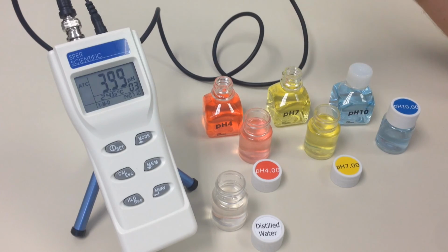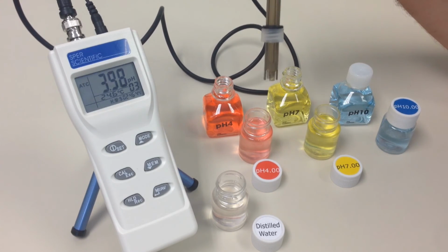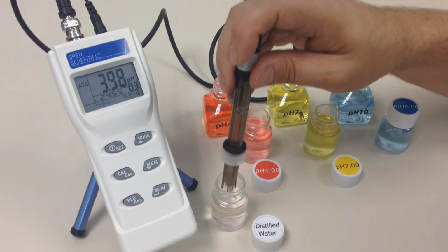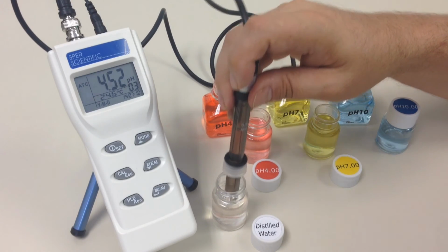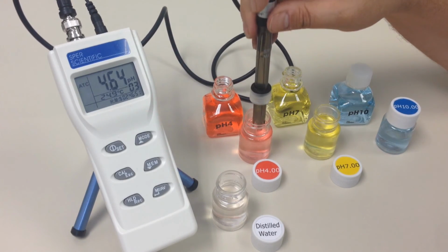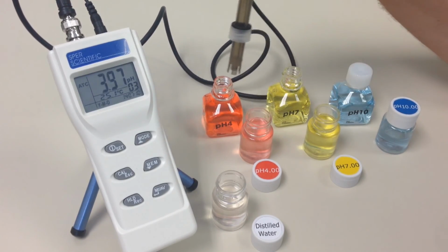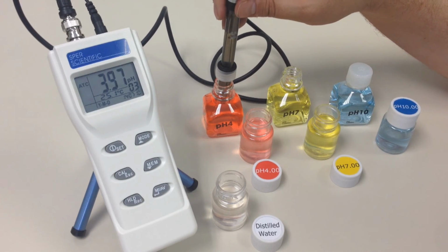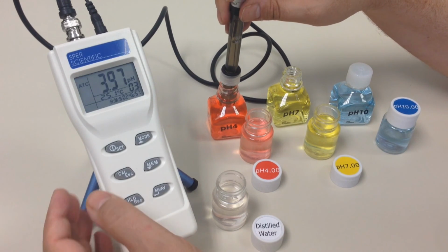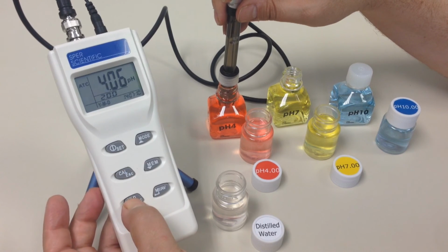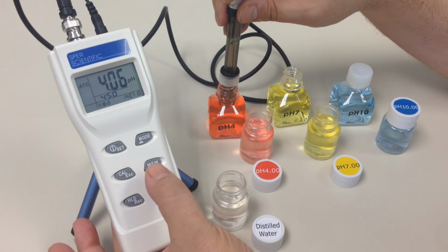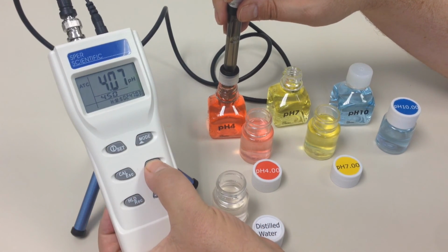Okay, now we're going to go ahead and do the second point, which is pH 4. So I'm going to clean off the probe using distilled water, put it in my first bottle of solution. I'm going to put it in my actual calibration bottle again. I'm going to hit the Cal button. Hit the hold button. 4.50 is going to appear on my secondary screen. I'm going to lower that down to 4.0 since that's my target.